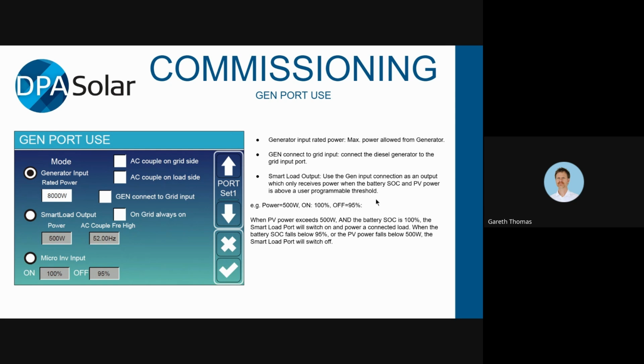Smart load output. So use the generator input connection as an output, which only receives power when the battery state of charge and PV power is above a user programmable threshold. So it's basically saying this is like AC out 2 on a Victron, perhaps. You can set some conditions for an AC output to be on or off. So the example that we've got here is you set power to 500, on to 100%, and off to 95%. And that means that when the PV power is greater than 500 watts and the battery state of charge is 100%, it will turn the smart load on. When the battery falls below 95 or the PV power falls below 500, then the smart load will switch off.